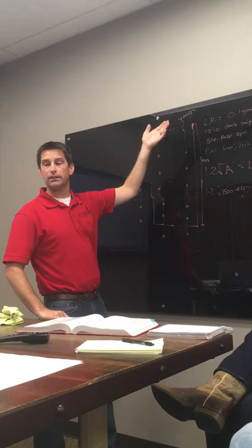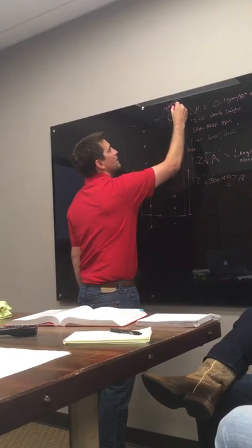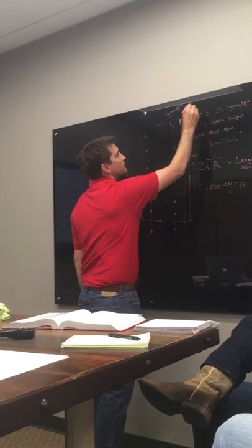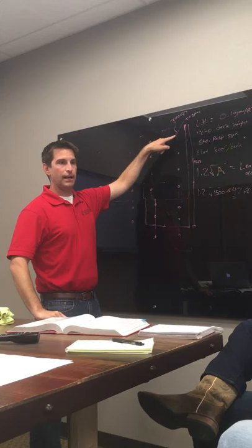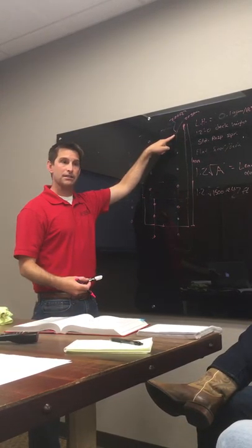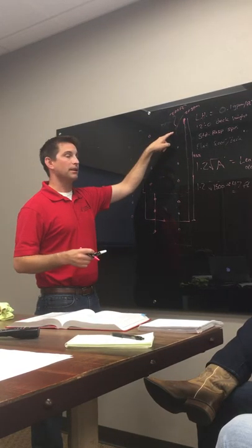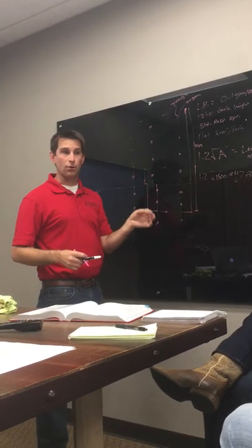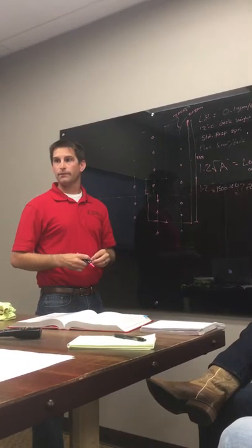20 gallons a minute. 20 gallons a minute, right? So in order to achieve that density, I need 20 GPM. If I need 20 GPM to that sprinkler, now I need to know what the K factor is, so I can figure out the pressure I need to push 20 gallons a minute through a certain size hole, which is your orifice, which is what the K factor is representing. So what is the K factor?